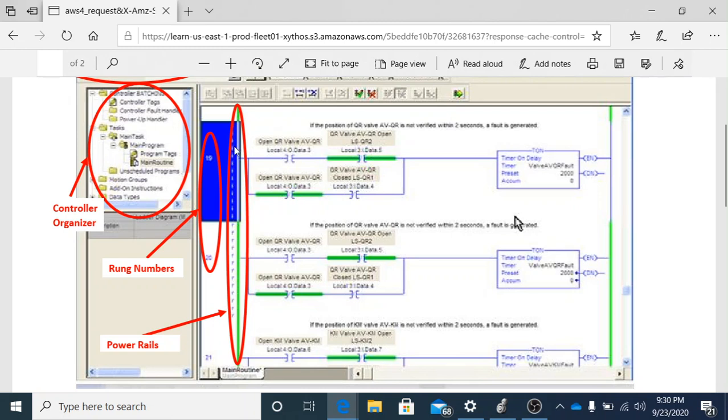Well, when it's in edit mode, these eyes indicate the rung that you're changing, because if you look at this rung and this rung, they look the same. And that's because at this point in time they were. So this is the rung that you're working with, that you're changing. This right here is a copy of that same rung. So while you're editing, it's running the previous version here. That's why it's green. It has the R's for running. And this up here is gray, meaning it's not actually executing at the time.